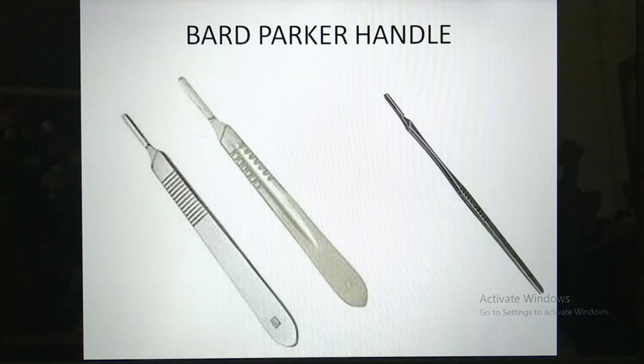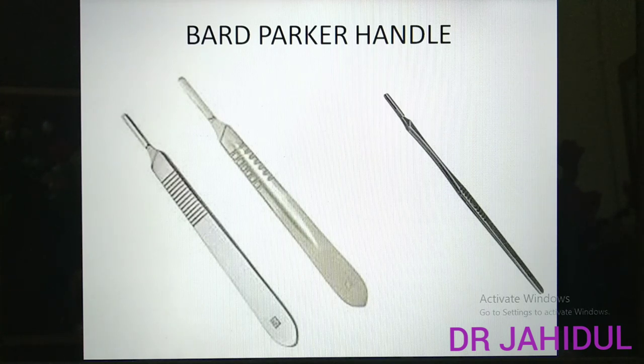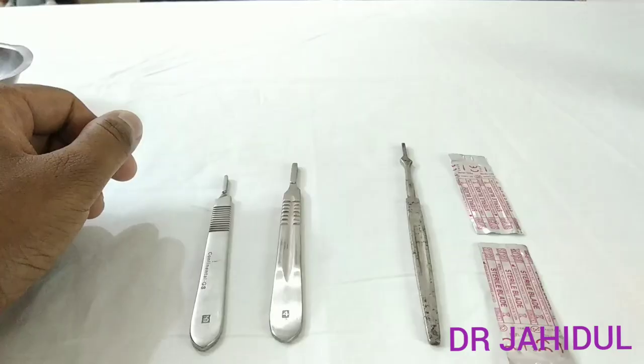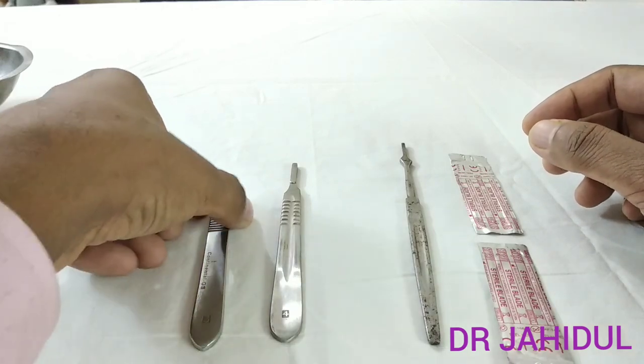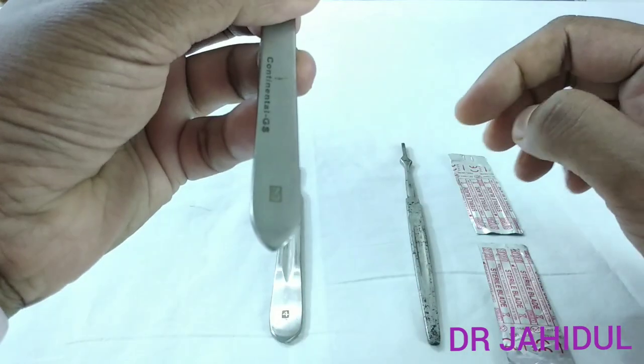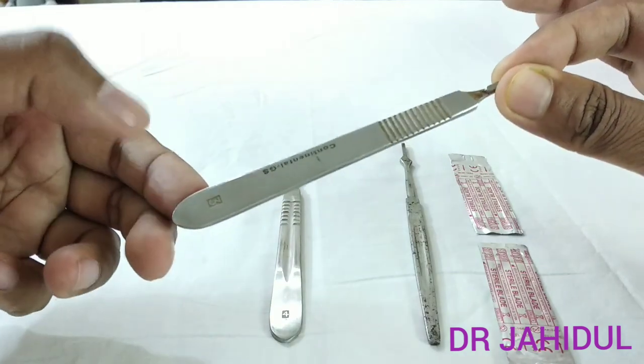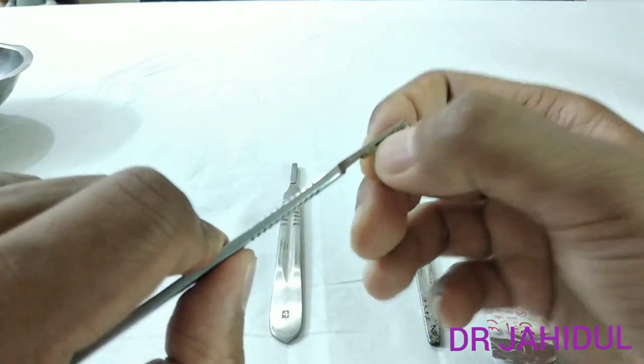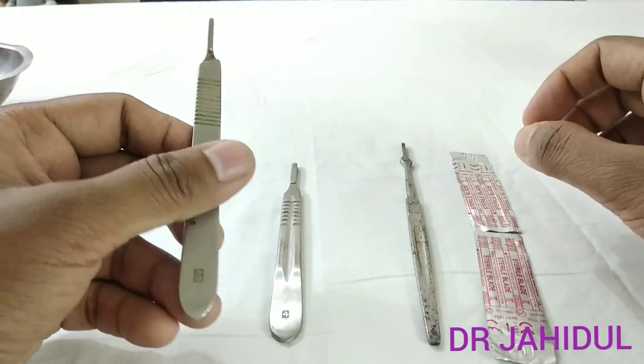First we shall discuss the Bard Parker handle. It may be different sizes written over its body — number 3, number 4 are commonly used, and also number 5 and 7. These are attached with a surgical blade. The BP handle is a flat instrument with one side narrow, and there is a slot in the narrow side on both sides for engagement of a BP blade or surgical blade.